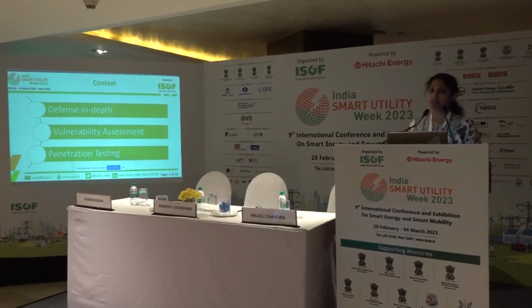Encryption is not allowed in such a situation because GOOSE packets' response and transmission time should be less than 3 milliseconds, which makes it quite difficult to protect. Thus a defense in depth mechanism is what needs to be practiced in any digital substation.